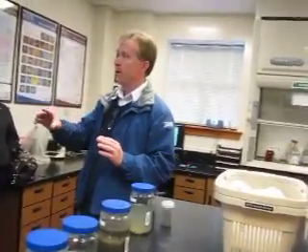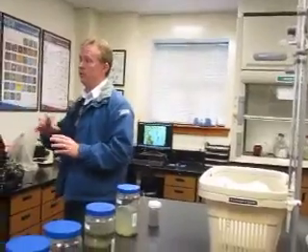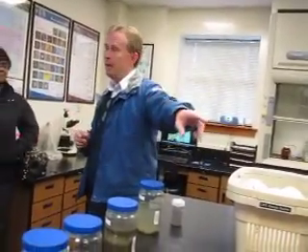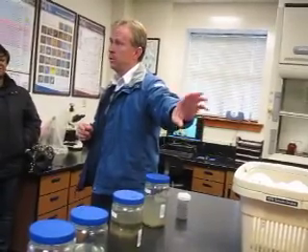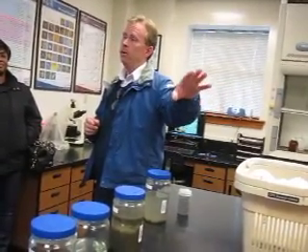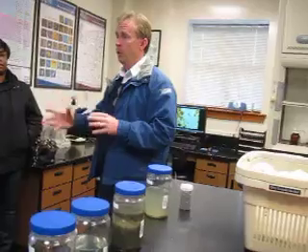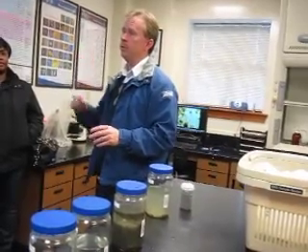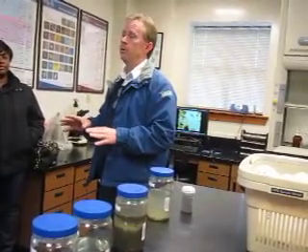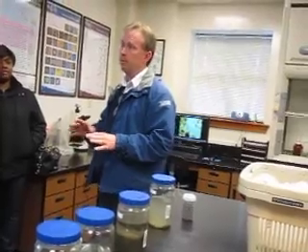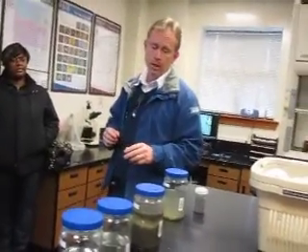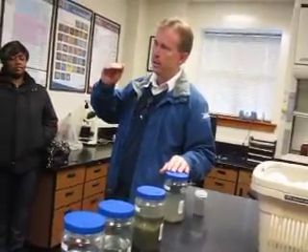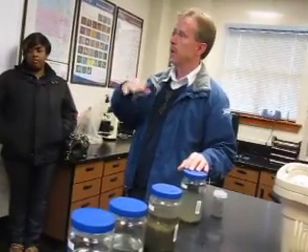So the operator sees it, he's going to go start collecting samples and make sure that's a true value. He'll collect a sample, come back in here and run a lab test to see what the pH is. If it's truly below 5.9, then we're on the lookout. We start collecting other samples and making any process control changes we may need to make, and be watching out for other problems. And if that pH gets above 8, it'll do the same thing.